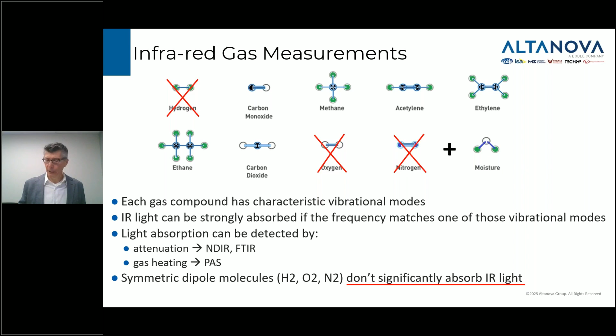One limitation of the infrared measurement methods, however, is that there are certain gases that simply don't absorb the infrared light significantly. And so multi-gas monitors that use these infrared methods have to use other sensors, other ways to measure hydrogen, oxygen, and nitrogen, because they don't have any signature in the infrared measurement method.